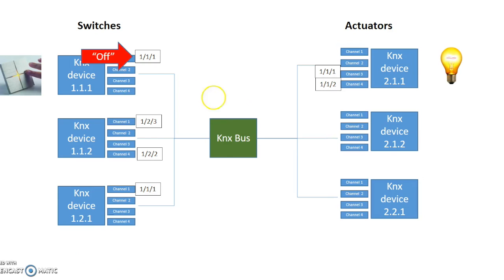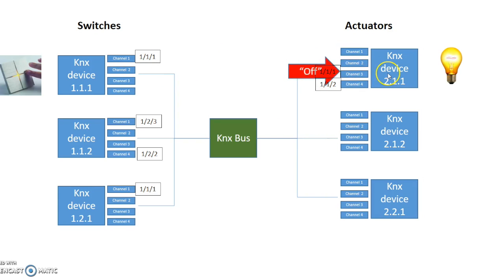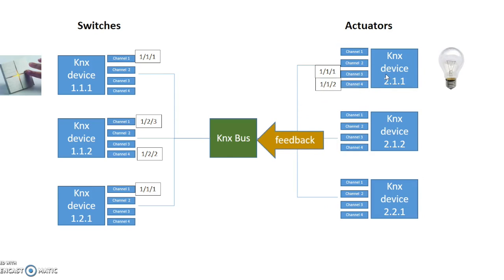If you want to switch it off, an off-value is sent to the group address, which again travels through the bus to channel 3, turns off the light, and feedback comes back to confirm everything is switched off. That's fundamentally how KNX works: we have devices, each device has a programming address, each device has a series of channels to which group addresses can be assigned, and all that happens is an exchange of information between the switches and actuators, all linked by those group addresses.